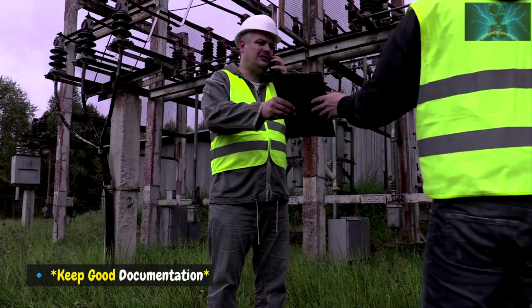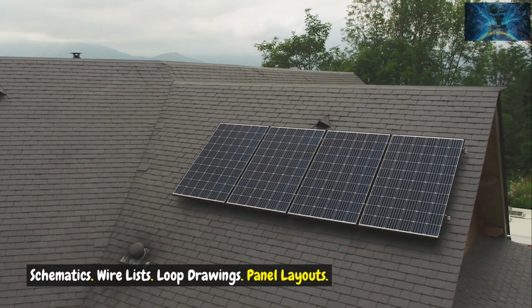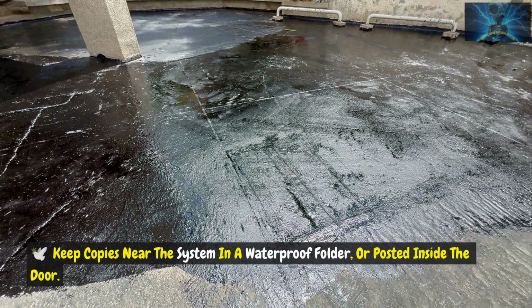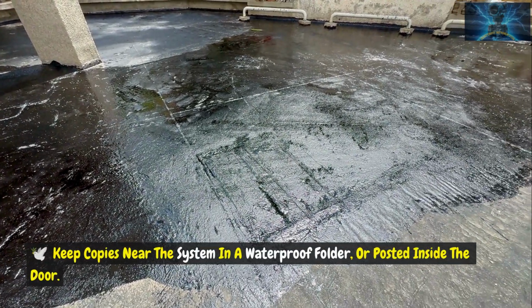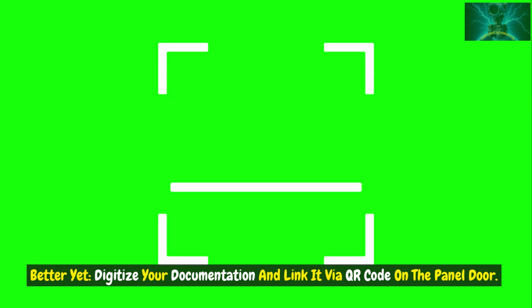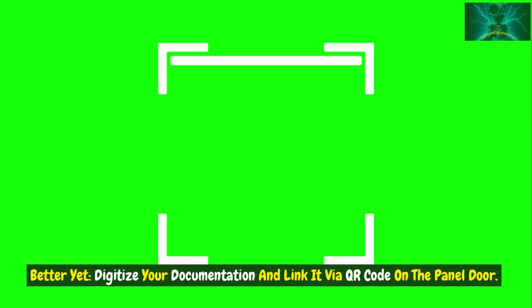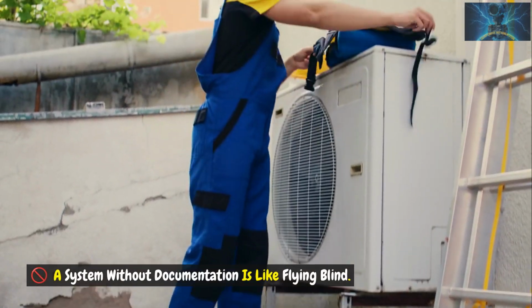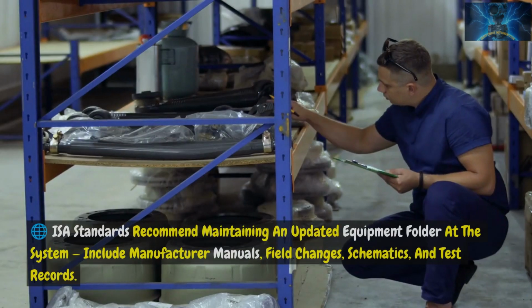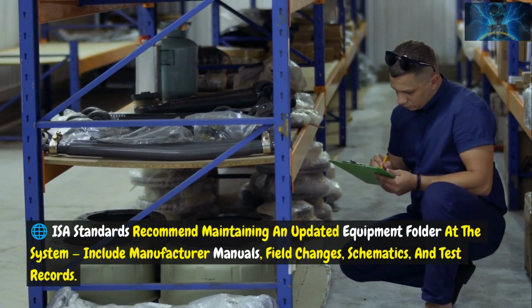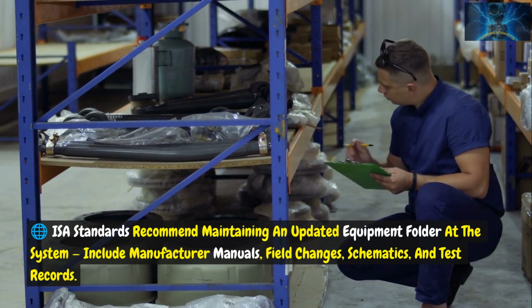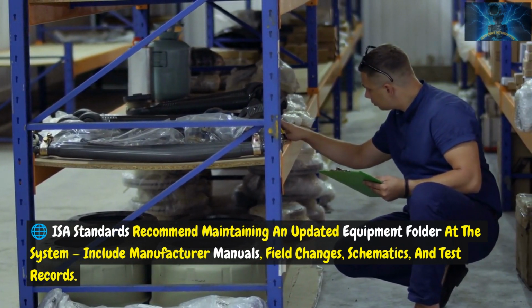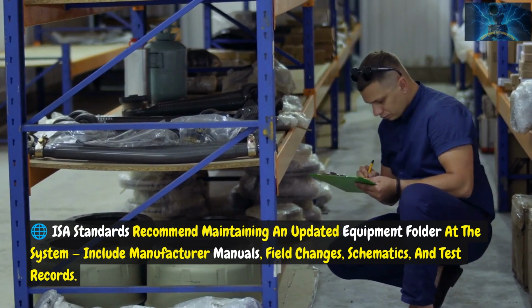Keep good documentation: schematics, wiring diagrams, loop drawings, panel layouts. Keep copies near the system in a waterproof folder or posted inside the door. Better yet, digitize your documentation and link it via QR code on the panel door. A system without documentation is like flying blind. ISA standards recommend maintaining an updated equipment folder at the system. Include manufacturer manuals, field changes, schematics, and test records.